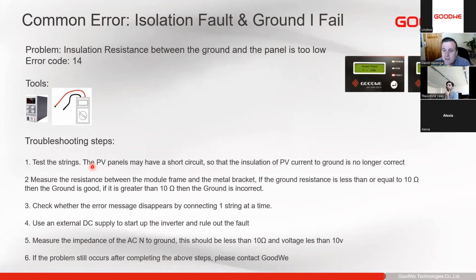So we can check our strings one by one: remove all the strings from the inverter, connect one string up to the inverter, and see if the error is still there on one single string. We try a different MPPT as well to see whether it appears on one MPPT but not the other. So with one string at a time, we can test that. If there is an isolation fault on one specific string, we can find which string it's on, and then we can do all the fault finding on that string.